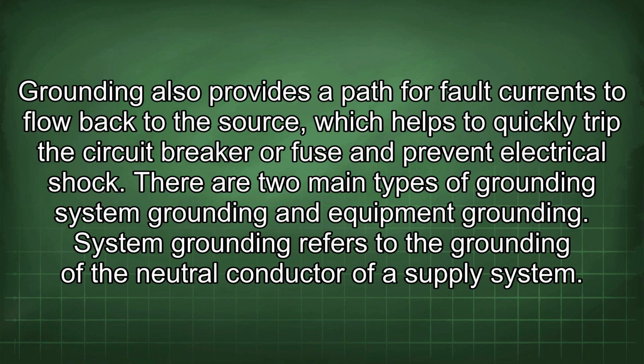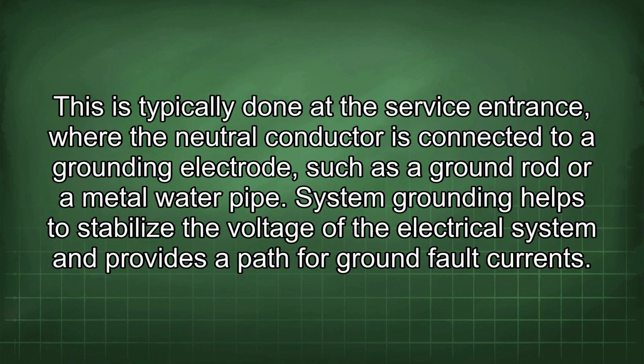System grounding refers to the grounding of the neutral conductor of a supply system. This is typically done at the service entrance, where the neutral conductor is connected to a grounding electrode, such as a ground rod or a metal water pipe. System grounding helps to stabilize the voltage of the electrical system and provides a path for ground fault currents.